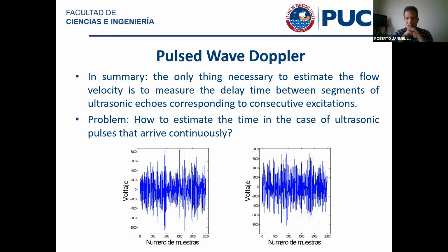So the signal being generated comes from a set of particles that are continuously leaving the field of view of your transducer. Whether you like it or not, the signal is going to change. Even if they were running at the same speed, eventually it will change. Maybe you have 100 red blood cells generating the first echo, then because they're moving, 3 of those red blood cells are no longer in the picture, and you have maybe 3 new ones in slightly different locations. So the new echo looks slightly different than the previous one.